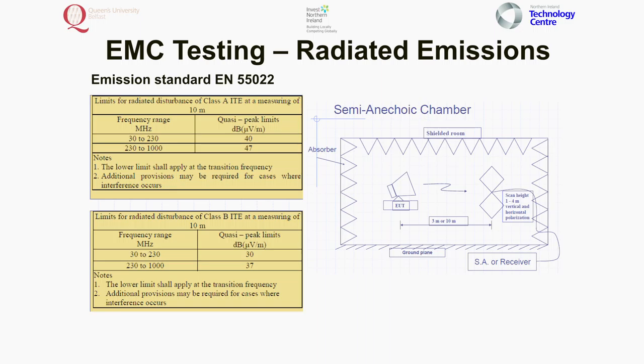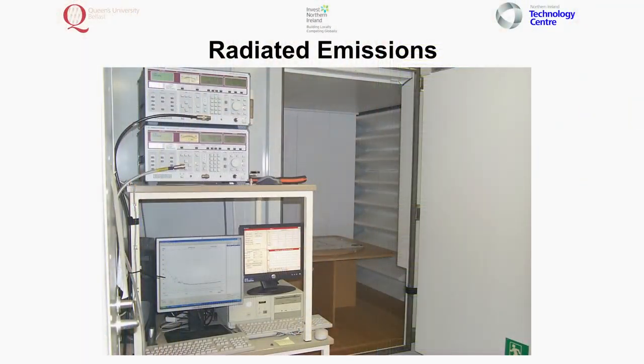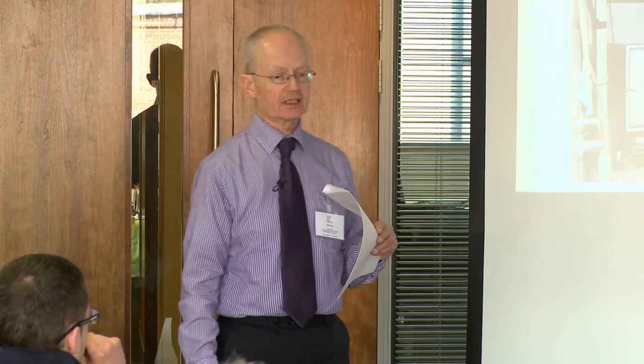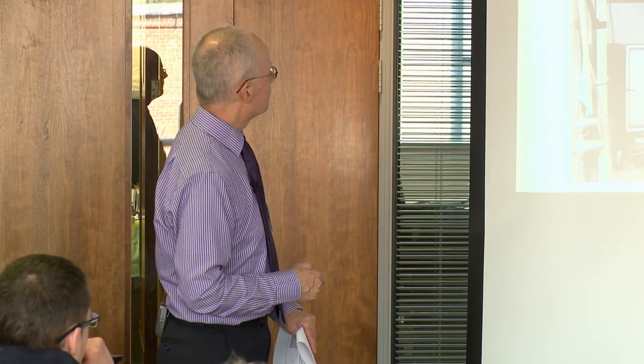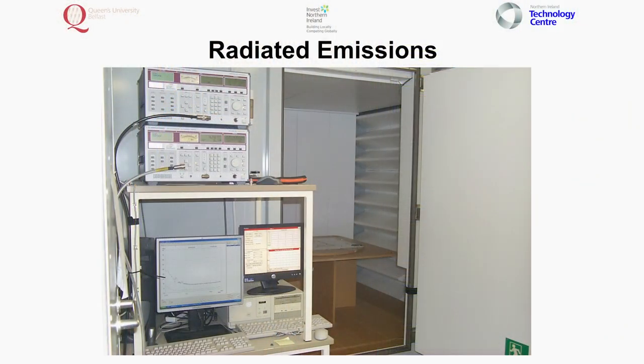When it comes to testing, there are something like 12 tests which I'll go through shortly. I'm going to start with radiated emissions. The basic standard is 55022 — or one of the basic standards. This specifies one of the ways it can be tested: at 10 metres, 5 metres, or 3 metres. These limits apply across the frequency range shown, and they're different for Class A and Class B.